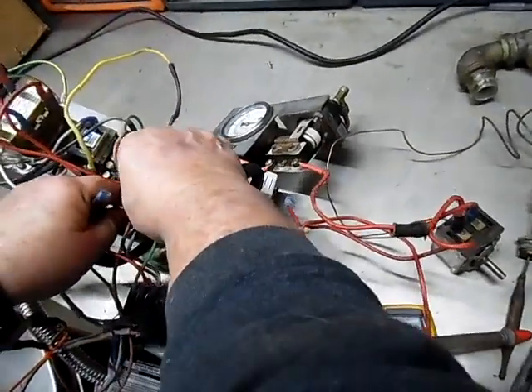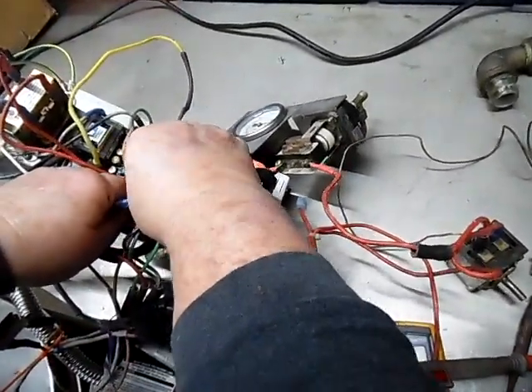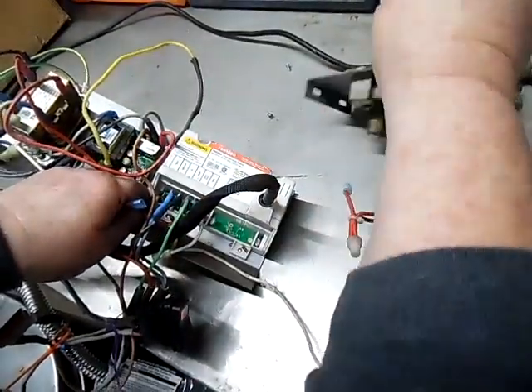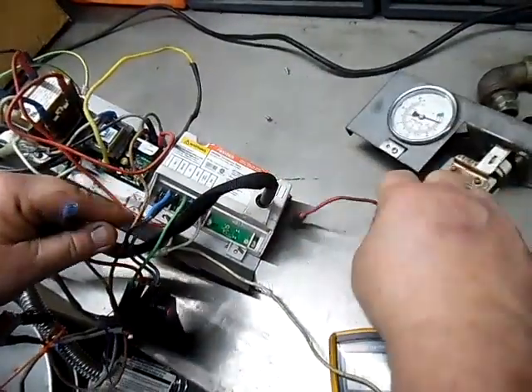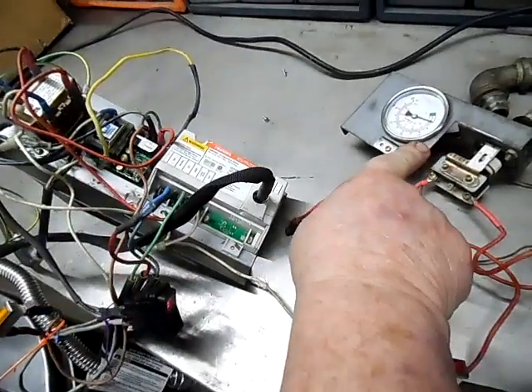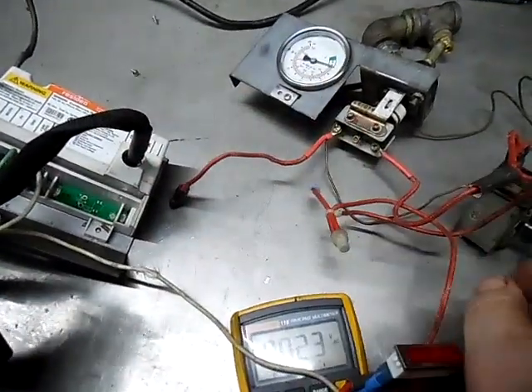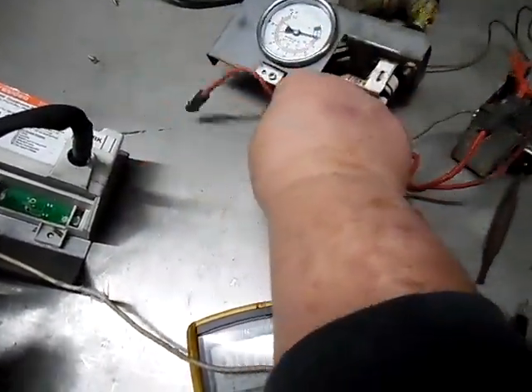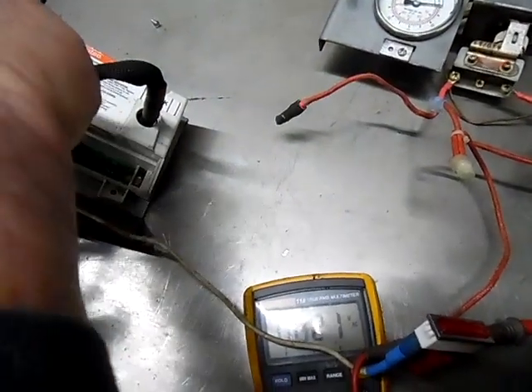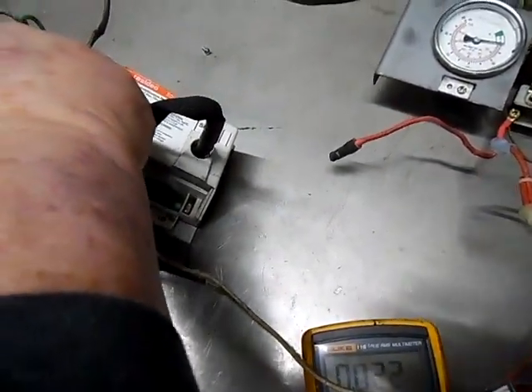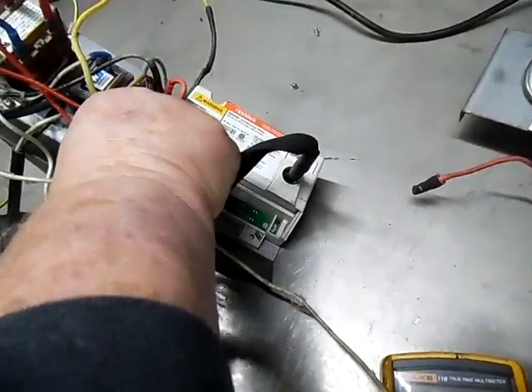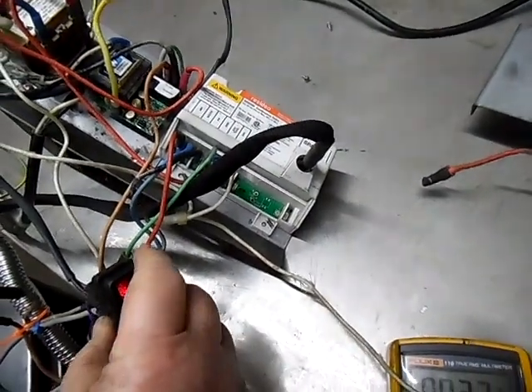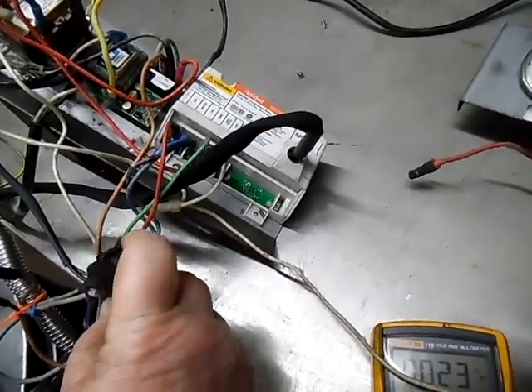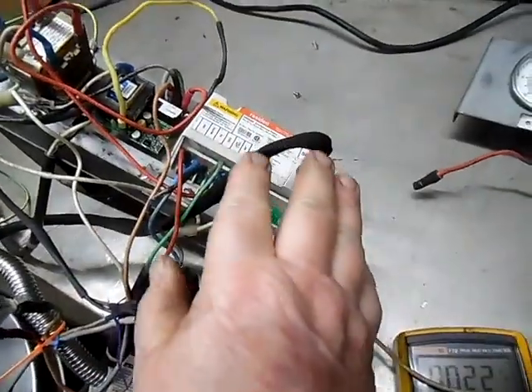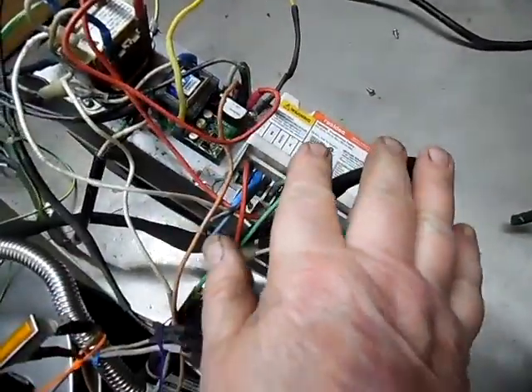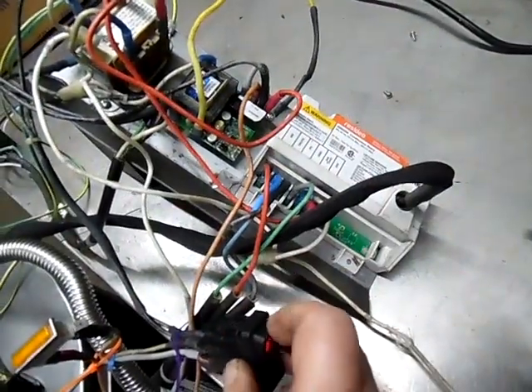I'm going to take the MV off the board. And if you notice, it's all tied to all this here, and it's tied to your pressure switch in here. I'm eliminating that. I'm going right to MV. So now when I turn this on, as soon as it sees that flame, it's going to come on and it'll stay on. So you don't do this either. This is only for testing. If you did, this thing would run non-stop.